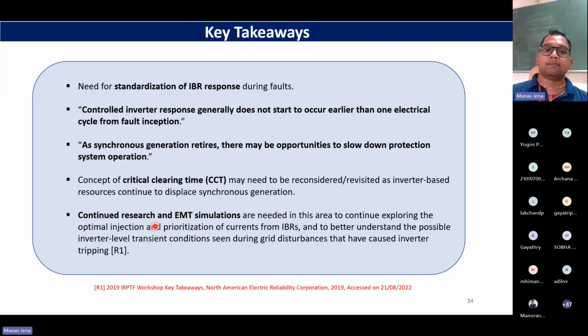But with all these inverters getting integrated, almost all the operators are now saying no, we should go for EMT. And then there is a trade-off. Can I model the whole grid with EMT? That's where co-simulation comes into the picture. Where you model the inverter and its control part in EMT, and the rest of the grid can be modeled in an RMS simulator. So it's called hybrid simulation. That can also be attempted, but continued research in EMT is definitely required.